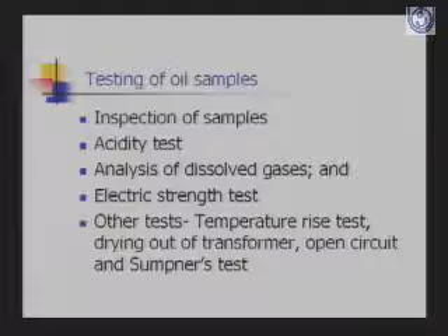So when we are talking of inspection of oil samples, then you see the oil for cloudiness. If it is cloudy, then there is suspended solid matter such as iron oxide or sludge in the oil. If it has a muddy color, then there is moisture ingress in the oil. If it is dark brown in color, then it indicates presence of dissolved asphaltenes. These are molecular substances that are found in crude oil, consisting primarily of CHNOS with traces of V and Ni.